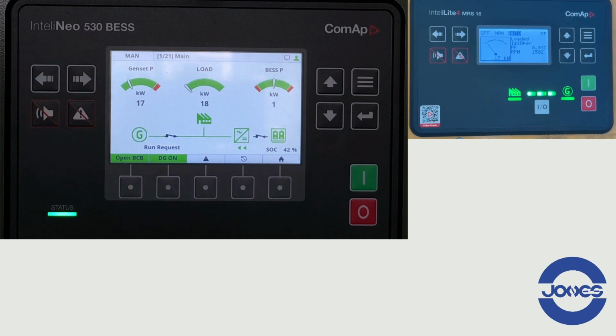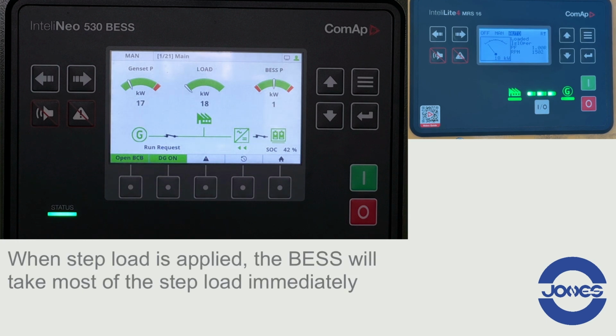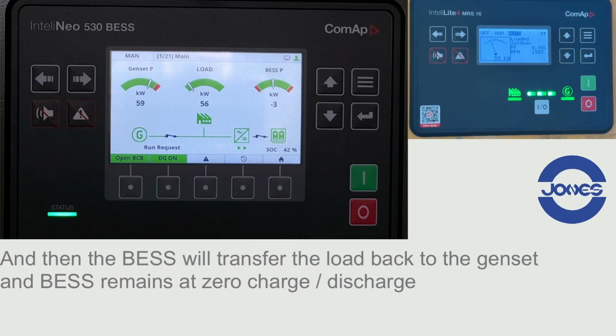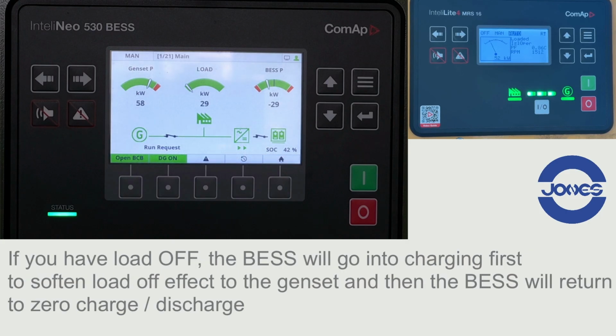When load step is applied, the BESS will take most of the step load immediately, and then the BESS will transfer the load back to the genset, and the BESS remains at zero charge discharge. If you have load off, the BESS will go into charging first to soften the load off effect to the genset, and then the BESS will return to zero charge discharge.